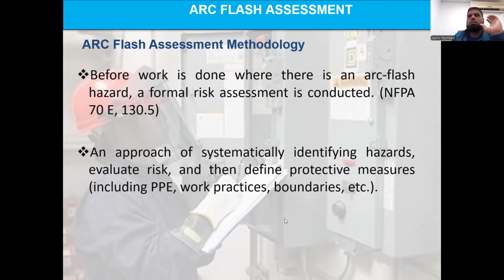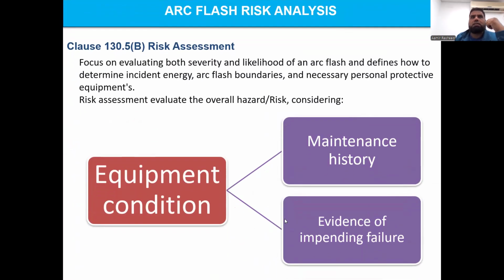This process, NFPA 70E 130.5, includes identification of the hazard, estimation of the likelihood and severity, determining the protective measures, establishing boundaries, selecting the PPE, and labeling the equipment. The purpose is proactive risk management, not reacting after an incident. In the arc flash risk assessment analysis, we evaluate both severity of the injury and likelihood of occurrence.